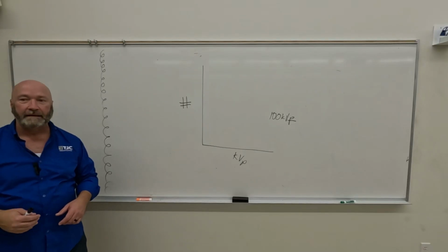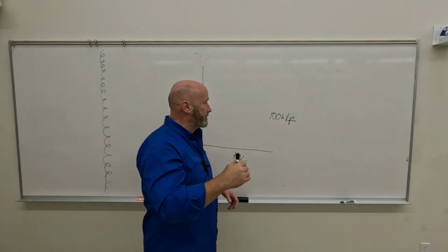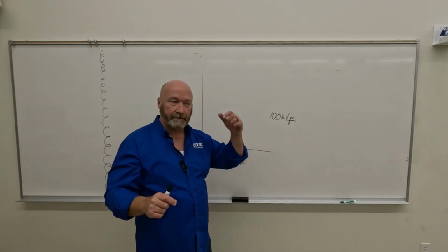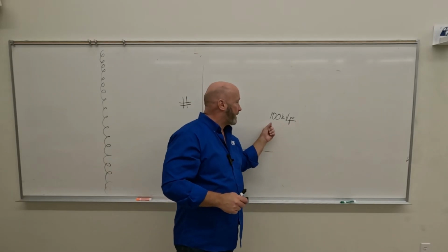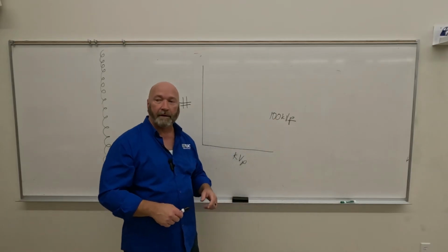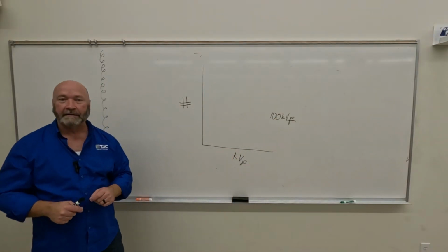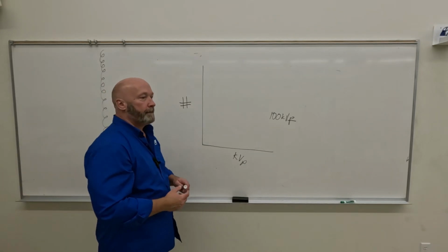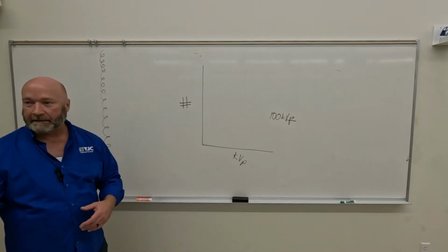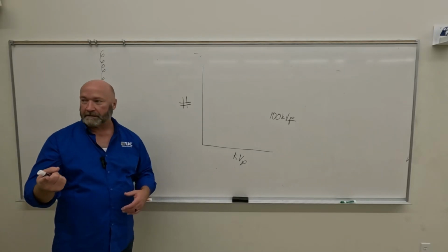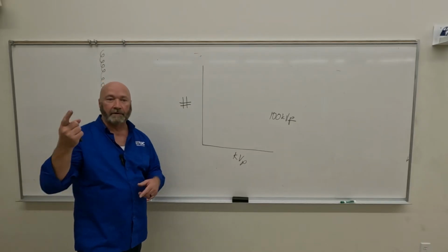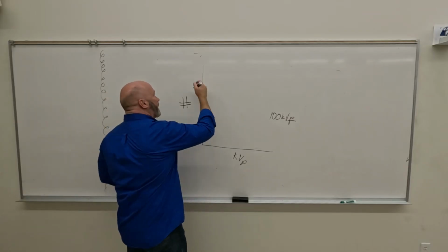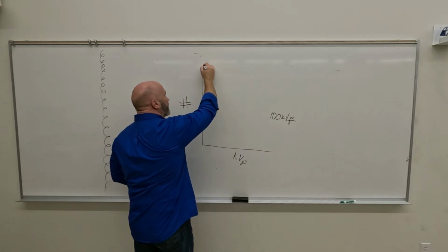So if you set 100 kVp, and an electron comes in and loses 100% of its energy in a single shot, that's only going to happen by brems. Then what we're going to create is a 100 kVp X-ray photon. But we're shooting tiny things at tiny things. So how many of those do you think we're going to get? Very few, right? So we've established that you're going to create a lot of low energy X-ray photons because you're shooting tiny things at tiny things. We're going to create very few high energy X-ray photons. So what our creation spectrum would look like then is this.